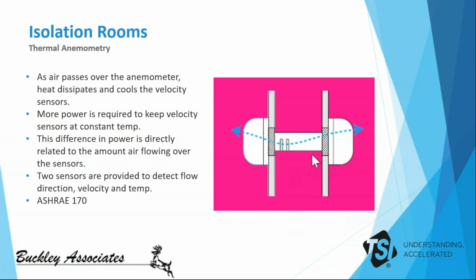So ASHRAE 170 requires that every isolation room has a permanently installed visual device or mechanism to constantly monitor the air pressure differential in a room. While the permanent device can be as simple as a flutter strip or a calibrated ball and tube, the most reliable way to measure and monitor room pressure is going to be with the use of an electronic pressure monitor. This is really the only way to do it. When properly installed, the monitor is going to be able to continuously provide confirmation at a variety of points, including pressure, temperature, and humidity in all these spaces. So even in temporary rooms, ASHRAE is still requiring some sort of pressure monitoring to allow all of the healthcare workers to know the status of the area that they're working in to ensure that it's still safe.